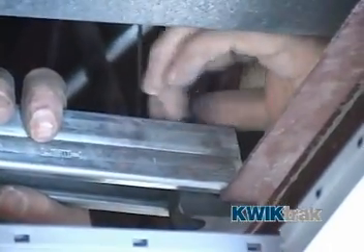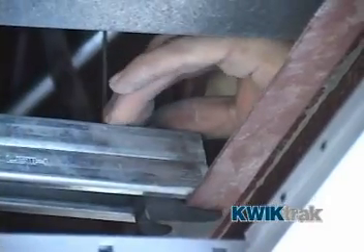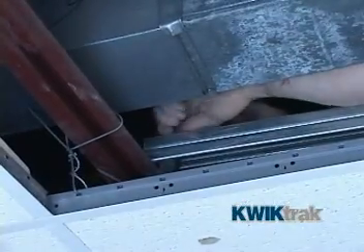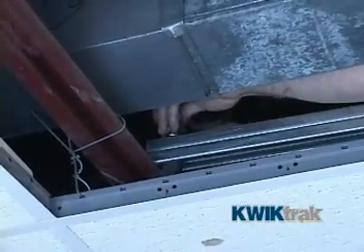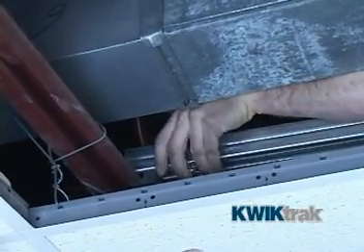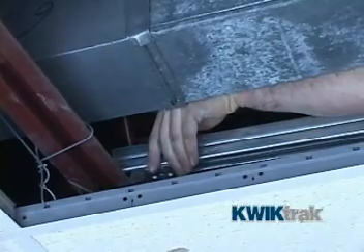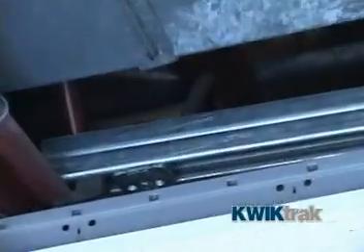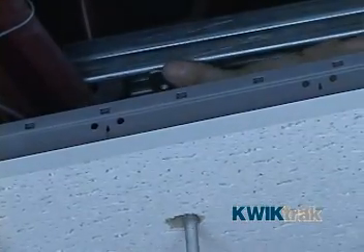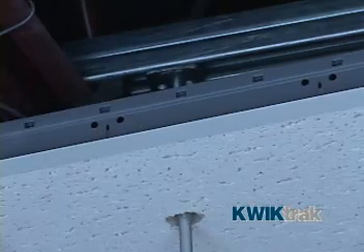If an obstruction above the ceiling will not allow conventional anchoring, and the bracket location falls between joists, Unistrut provides the solution. The secured Unistrut spans the joist gap, and with the use of a T-nut, the rod is threaded up through the strut and fastened in place.